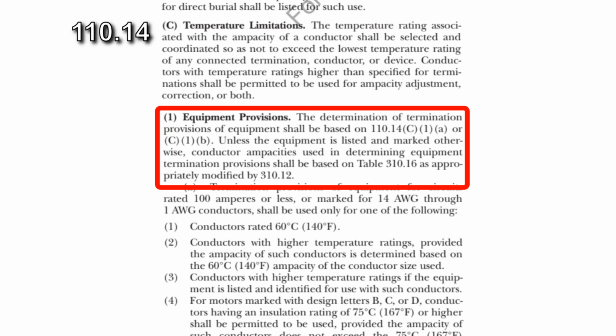110.14(C)(1) Equipment Provisions. The determination of termination provisions of equipment shall be based on 110.14(C)(1)(a) or (C)(1)(b). Unless the equipment is listed and marked otherwise, conductor ampacities used in determining equipment termination provisions shall be based on Table 310.16 as appropriately modified by 310.12.